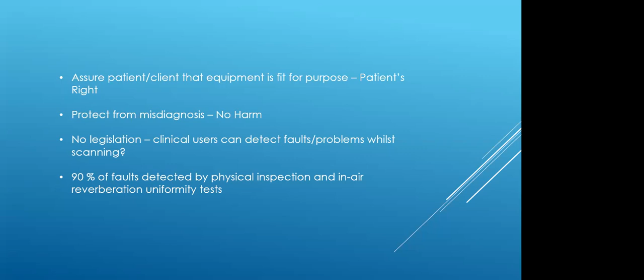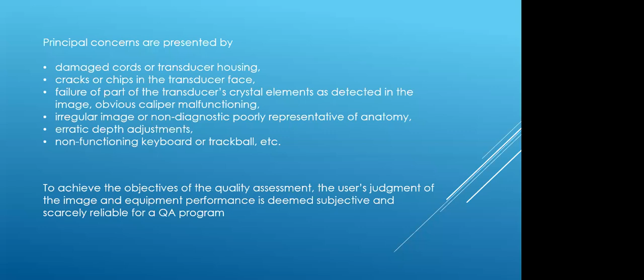Right. So the principal concerns, as I said, are the frayed cords. We could also have, for example, failure of the actual crystal elements, but you should be able to check whether they are failing or not. Have a method for that. You could have issues with keyboards or trackballs not working properly, which would give you problems in how you do a measurement when the trackball sticks or doesn't click in to pick up a point.